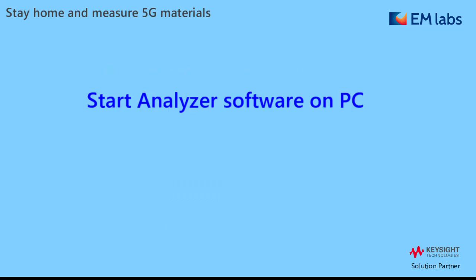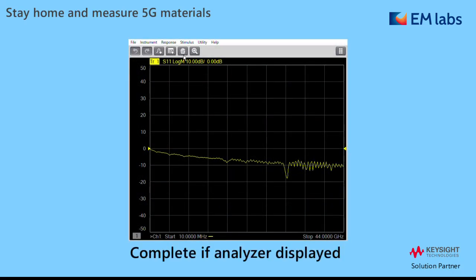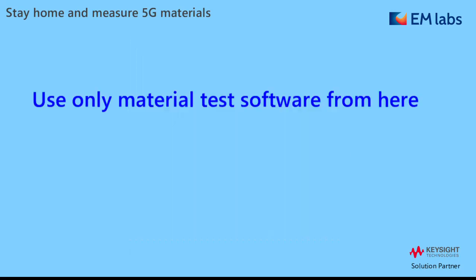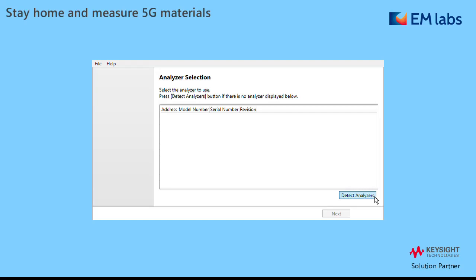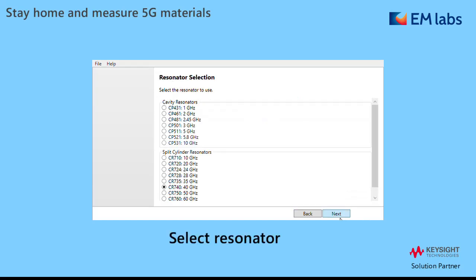Move on to software. Start the Analyzer on PC — it's a normal Windows application. Just start and follow the instructions and you'll see the analyzer display like this. From here we only use the material test software. Start the software, connect the analyzer for control, and select the resonator. There are options from 10 to 60 GHz, and we use the 40 GHz for 5G today.